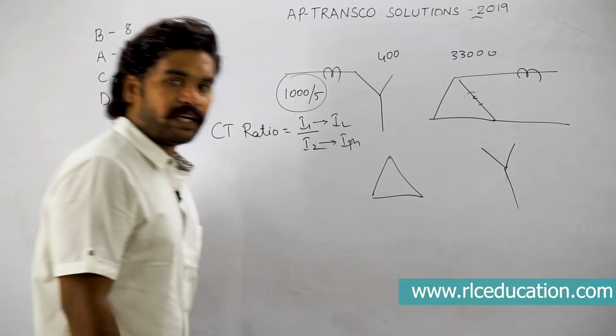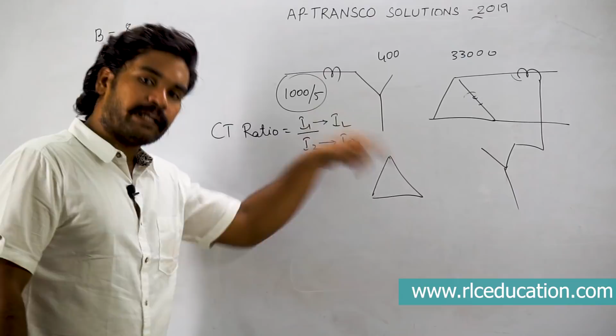So when you are mapping the transformer currents to the CT, the primary CT current corresponds to the line current of the transformer, and the secondary CT current corresponds to the phase current of the secondary connection. Understood? Because on the primary side you will place the CT in the line, not inside the phase winding, isn't it? Similarly here, we will place the CT in the line, not in the phase winding. So you're connecting the primary of the CT in the line, whereas the secondary becomes part of the phase. So the current ratio of CT represents the top one, that is I1 represents the line current of the main transformer, I2 represents the phase current in the CT connection.